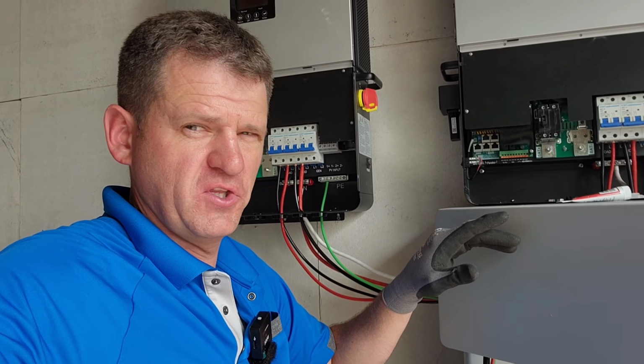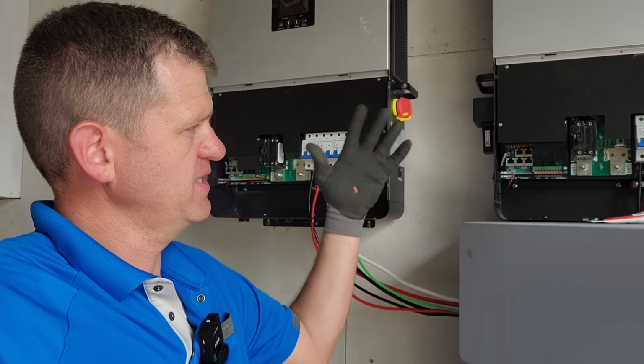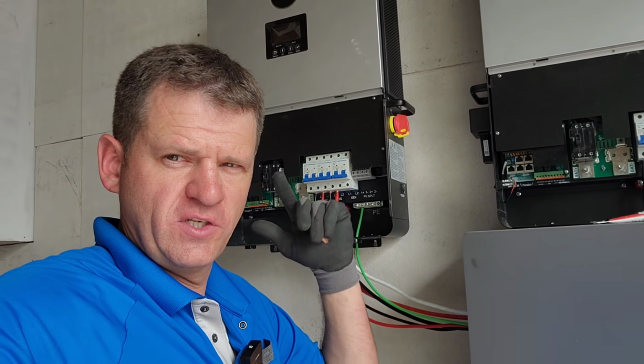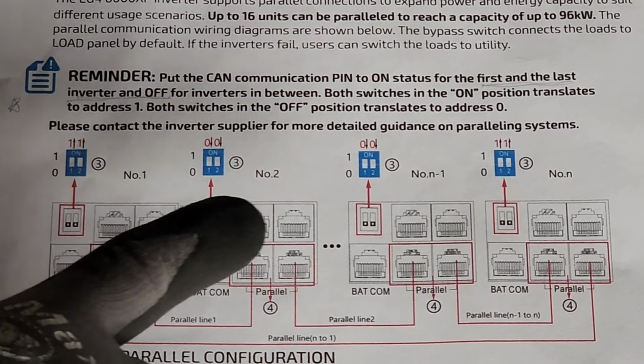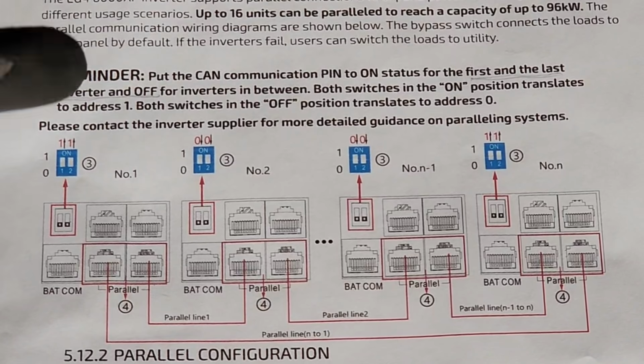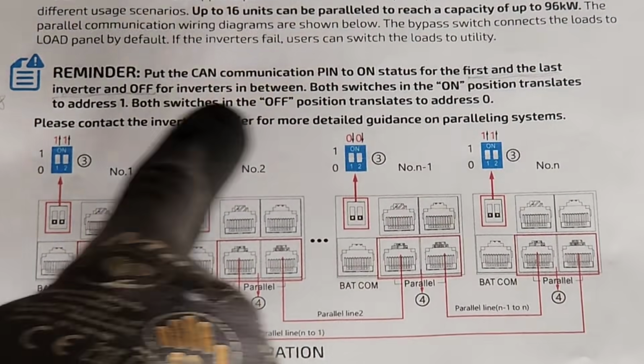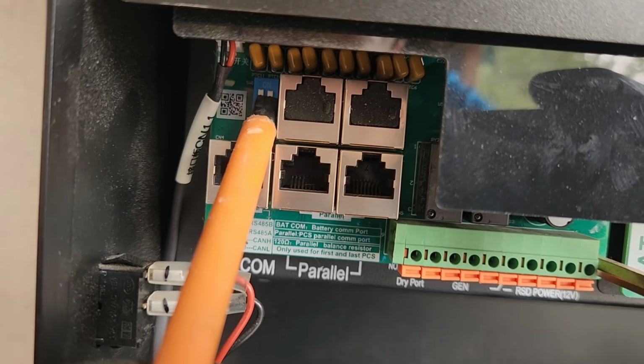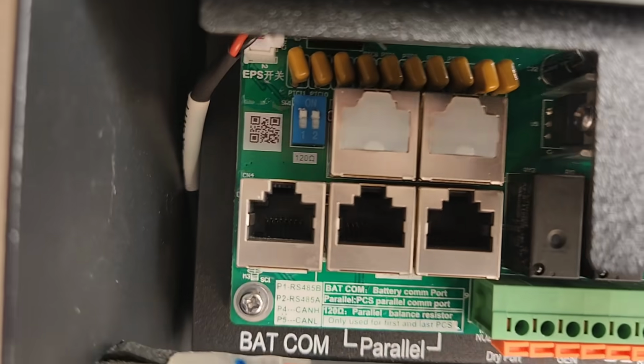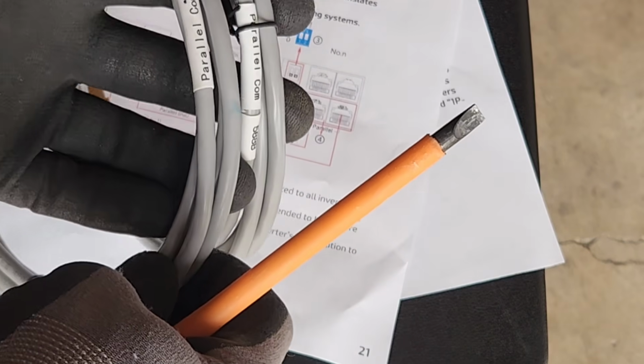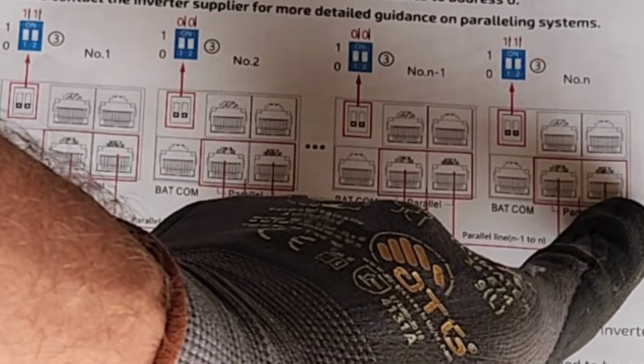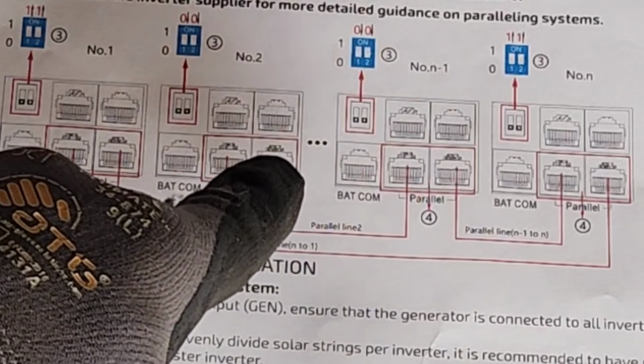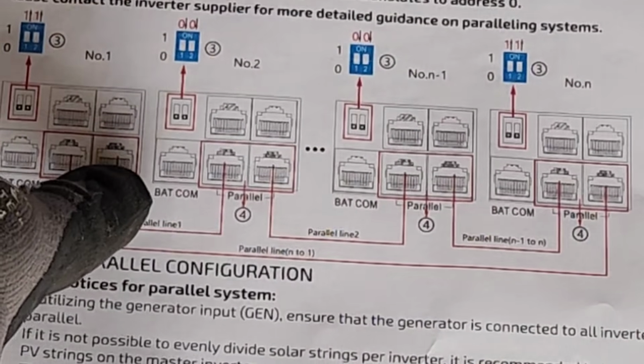Okay, so now for possibly the trickier part, I'm going to hook up the communication because as these are outputting power, they need to communicate. So let me check out the manual and we'll follow the manual, see how clear it is. Okay, so it looks like I can connect up to 16 units in parallel. And let's see, put the pin status to on for the first and last inverter. So that's both of my inverters are the first and last. So I'll do that now. There we go. Okay, I've got these 2 cables that came with each. Looks like the first inverter must connect to the last inverter here with the parallel cable. And then the last inverter connects up to the first inverter from here to here.